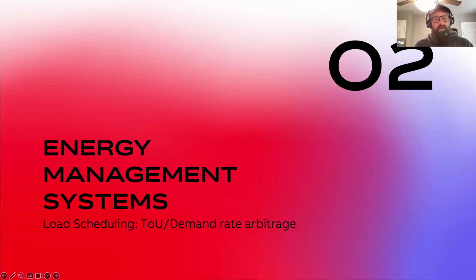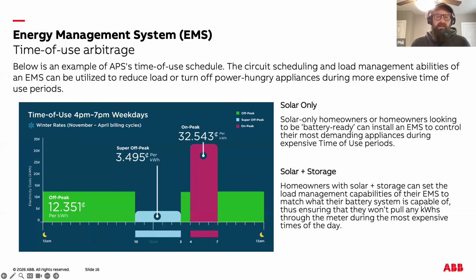These are non-overload control and are really just designed for rate arbitrage. So the first and probably most common example of EMS function that we're looking at is time of use rate arbitrage. The graph to the left of the slide is an example of APS, that's the Arizona utility. It's their time of use schedule. Certain types of EMSs can employ circuit scheduling and load management abilities to reduce load or turn off power-hungry appliances during more expensive time of use periods.